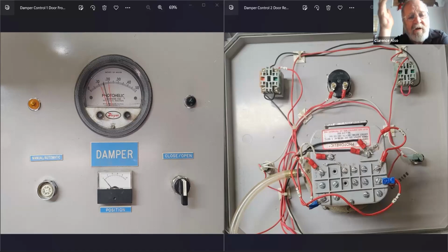So this is a big energy saving thing just based on how you guys operate your plant. Keep that in mind when you're adjusting this. What are you really doing? You're allowing the flow of air to go through your combustion chamber so you get the heat out that you need. If you're choking it up too much, that means you were too rich before, and you needed to lean it out a little bit.